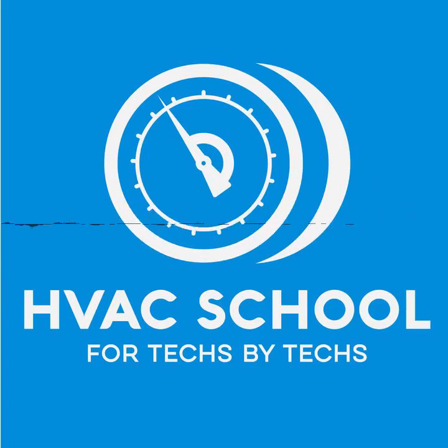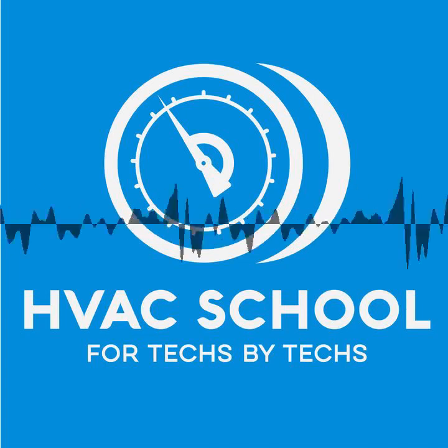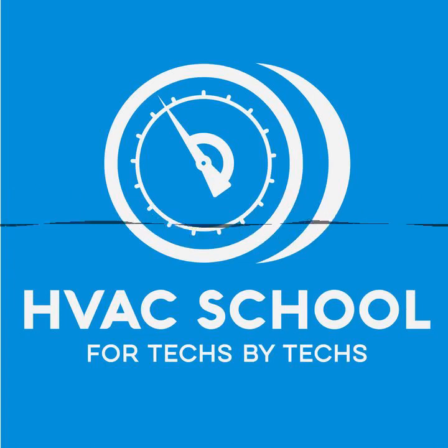Again, it's not ideal, but it works better than quarter inch hoses do for sure. It's not something that I would recommend. But if I was on a desert island and just had one Schrader core tool, then I would do it the way that they're suggesting. Yeah, there's nothing wrong with it. I wouldn't ever bash a guy because he does it that way. I'd be glad to see he's using a bigger hose rather than just vacuuming out one side, as long as you understand that if you've got a TXV that's a hard shutoff, you can't do that. Or a liquid line solenoid or something where you'd have to pull from both sides of the system, right?